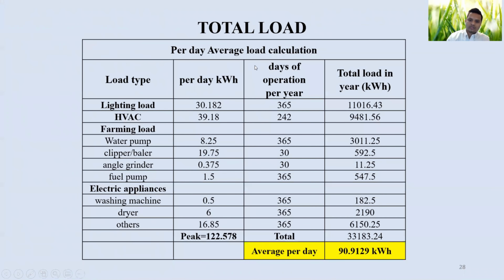In this way, the total load we calculated at the peak time came out to be 122.578 kilowatt hour, including lighting load, HVAC, farming load, and all the electric appliances. When we calculated this load, we knew that the HVAC load will not run every single day in the year. That will run only for 242 days in a year, but the lighting load will run for 365 days. In the same way, the clipper/baler will run only for 30 days when the farming work will be there. And other loads will run almost every single day in the year.